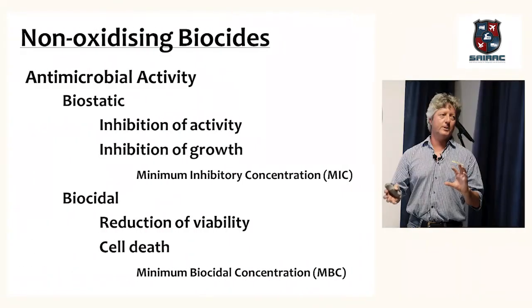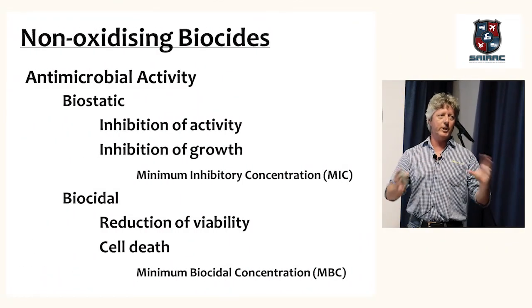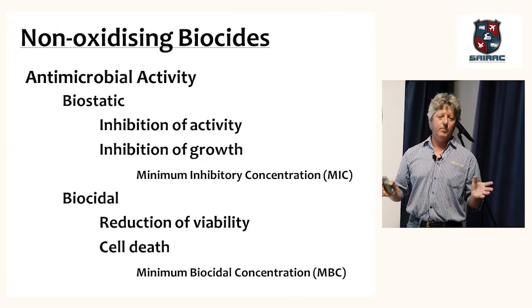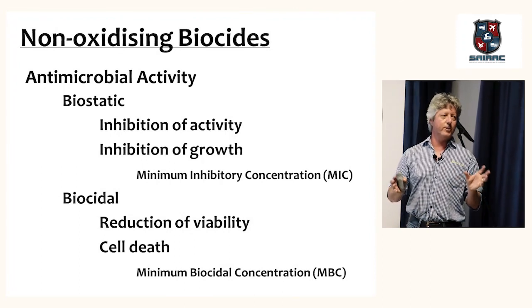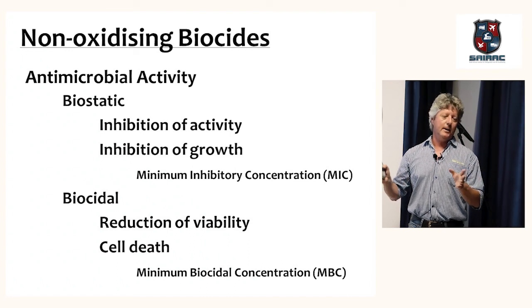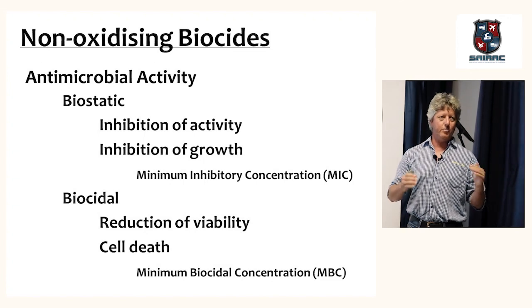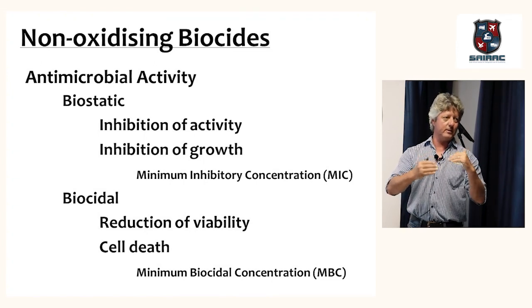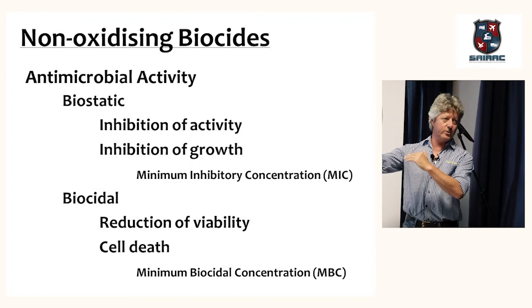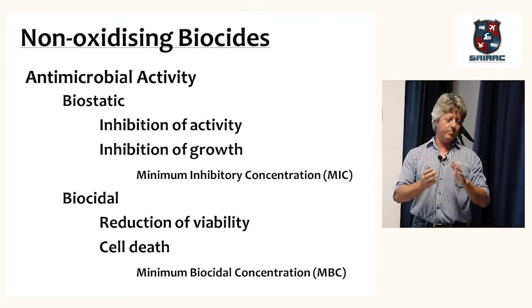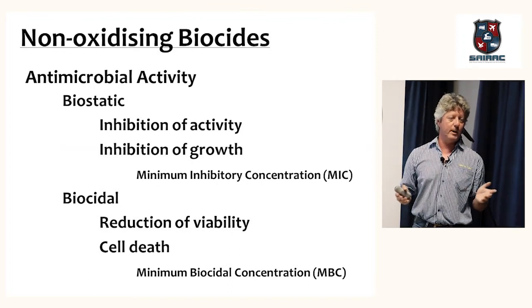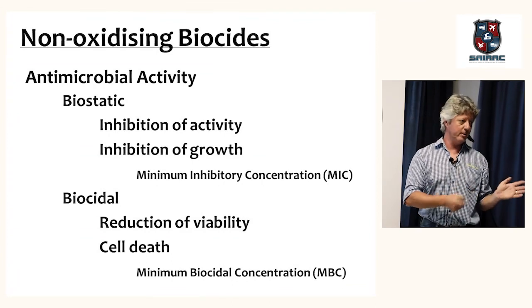If you use non-oxidizing biocides in a system, it's very good just to change them around periodically because of the dosing regimen of non-oxidizing biocides, you'll get a drop in concentration, and then the bacteria that survive that drop, they get more and more and more used to it, so that later on you have immune bacteria, then you need to put in a different one.